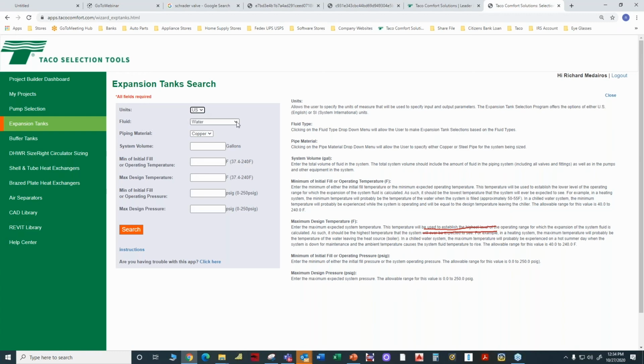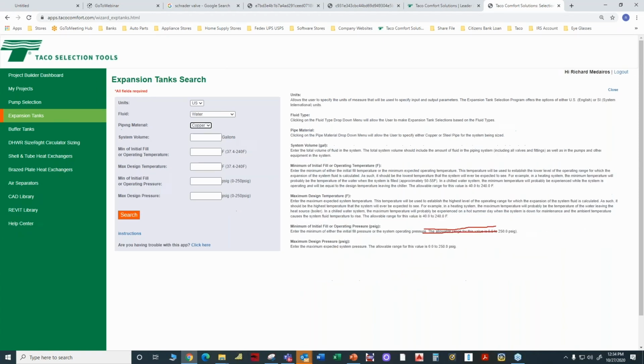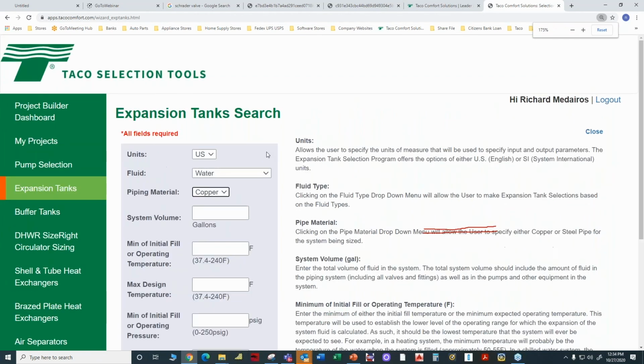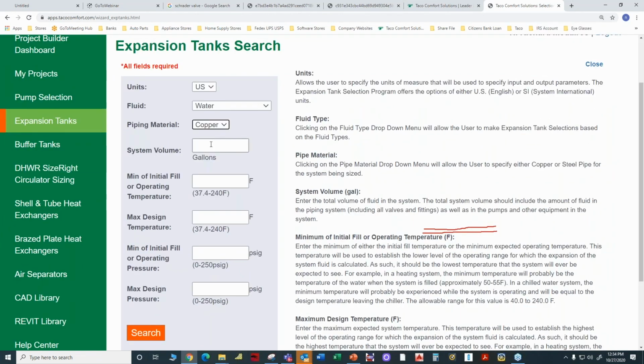Fluid, we're going to leave it at water for now. The piping material, I'm going to leave it at copper, and I'll show you our 2 choices are copper or steel, but I'm going to leave it at copper. The system volume is what we estimated, and we said that was 2,000 gallons. Let me zoom in a little so you can see. That's a little bit easier to read, right, Brett? Yep. So there's 2,000 gallons. The minimum or fill temperature in my case is 50 degrees. And again, that's dependent on where you are in the world. The maximum design temperature for my system is 180 degrees.